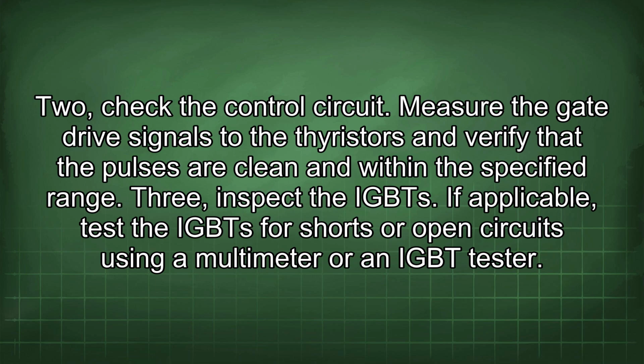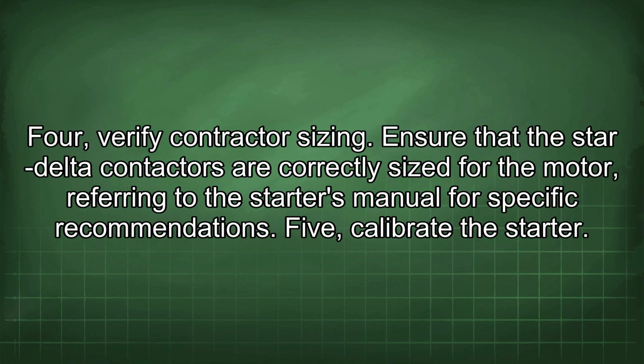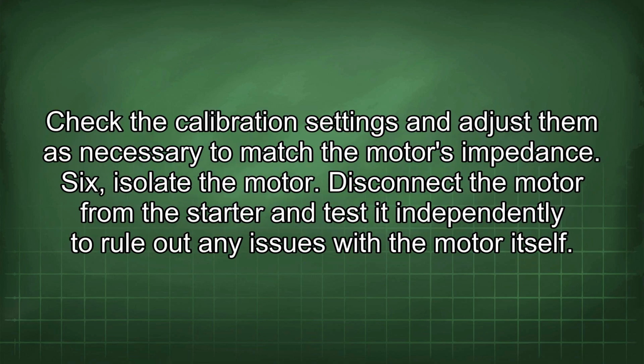3. Inspect the IGBTs. If applicable, test the IGBTs for shorts or open circuits using a multimeter or an IGBT tester. 4. Verify contactor sizing. Ensure that the star-delta contactors are correctly sized for the motor, referring to the starter's manual for specific recommendations. 5. Calibrate the starter. Check the calibration settings and adjust them as necessary to match the motor's impedance. 6. Isolate the motor. Disconnect the motor from the starter and test it independently to rule out any issues with the motor itself.